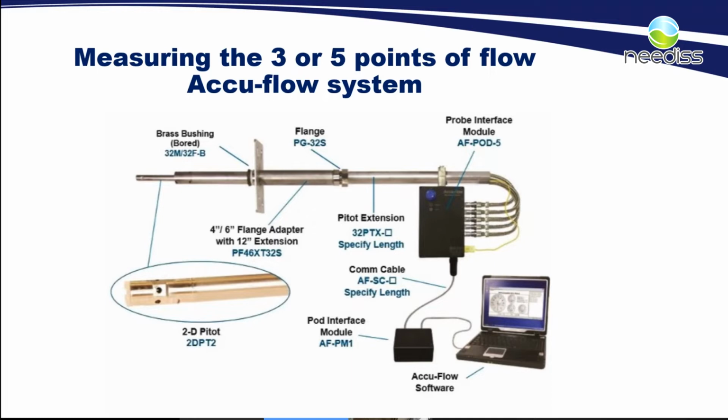Just like a mercury CEMS is typically calibrated, or in the US we say rated, relative accuracy test audit against the reference method, which is, in our case, the sorbent trap method, method 30B. You would take your 30B test and measure it against your mercury CEMS to calibrate its calculations. The same, we want to do that for our flow CEMS and the flow data that's being transferred into any CEMS system on a facility.